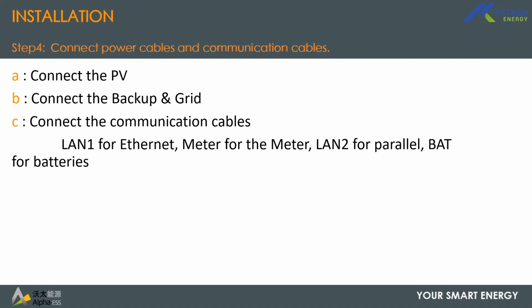And then soon after the meter, then your live wire, then you distribute it: one end goes to non-essential loads. That is the non-essential distribution port, where usually you have your inductive loads, your high power loads, that is the aircons, the stoves and the geysers. And then the other cable from the meter goes to the grid point of the inverter. So this grid point on the inverter is an output, sorry, when feeding the non-essential loads, and an input when it's drawing power from the Eskom to supply, either to charge battery or supply the essential loads.